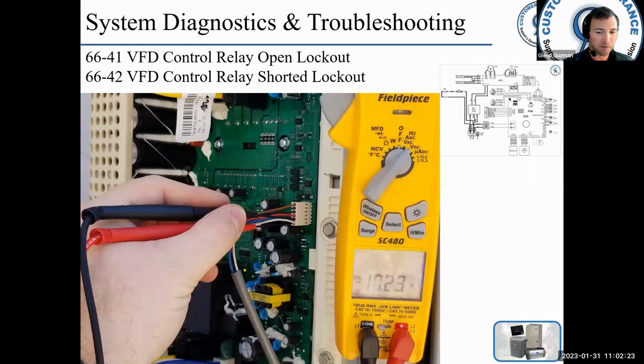Check your cable, make sure the cable is okay between the VFD and the PCM. If it's significantly more or less than 720 ohms, then the problem's the VFD, need to replace the VFD. Okay, so it's as simple as that. But you got to have the 12 volts, and then it's got to be pretty close to 720.